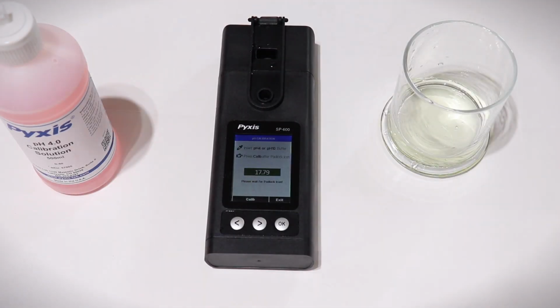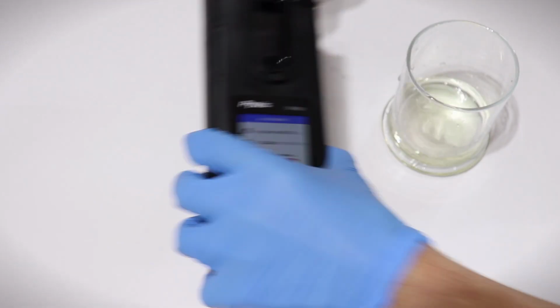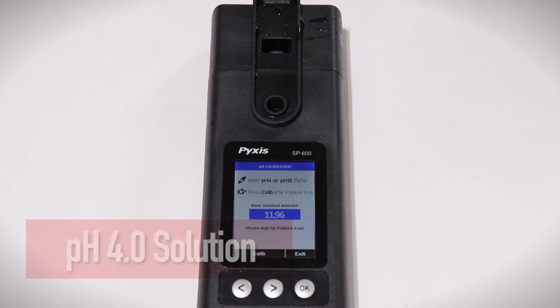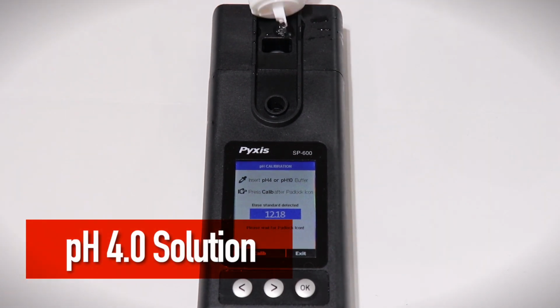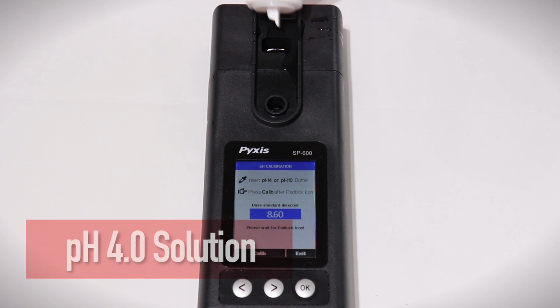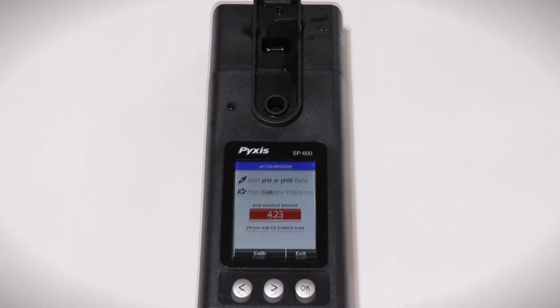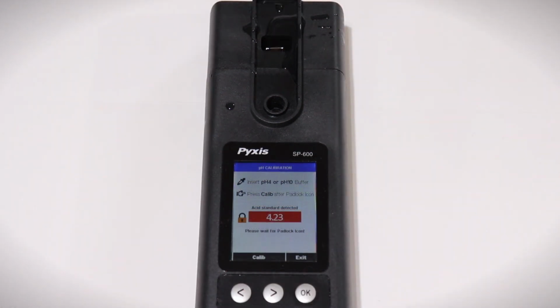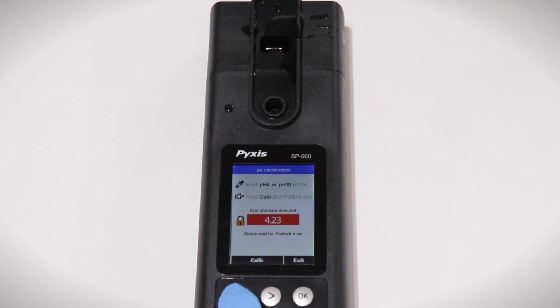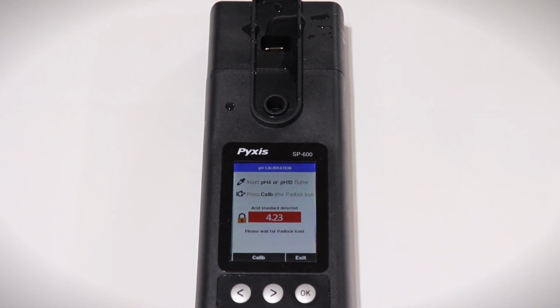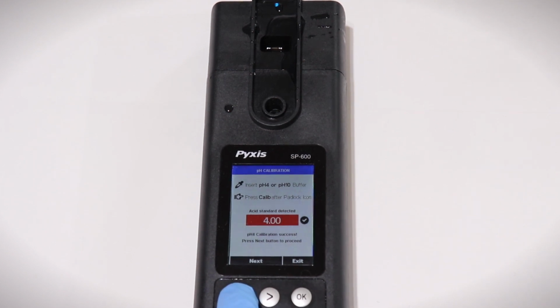Triple rinse the module with pH 4 calibration solution. Then insert pH 4 calibration solution and wait for the lock icon to appear. Then press either of the arrow buttons to select Calibrate. A success message will appear. Press either arrow button to select Next.